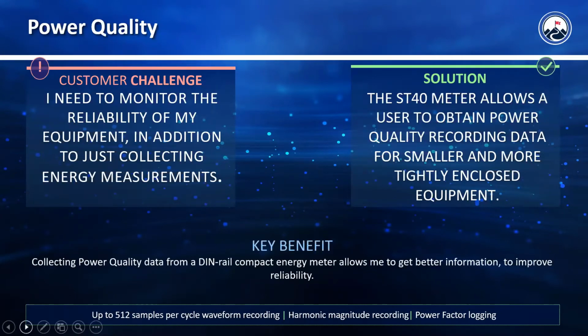Next, coming to power quality. When you have equipment that's worth millions of dollars and you want to be collecting your reliability information, your power quality information, in addition to your energy measurements, you can have all of the power quality capability in your meter. Even though you have a very tight space, you can get better information so that you can actually take steps to improve your reliability and protect your equipment from bad power being fed in. In addition to the 512 samples per cycle, this meter can also log your harmonic data, your power factor data. So you can look at if there are too many harmonics being fed into your equipment from the utility, or if your power factor is going down, causing your overall system efficiency to go down.